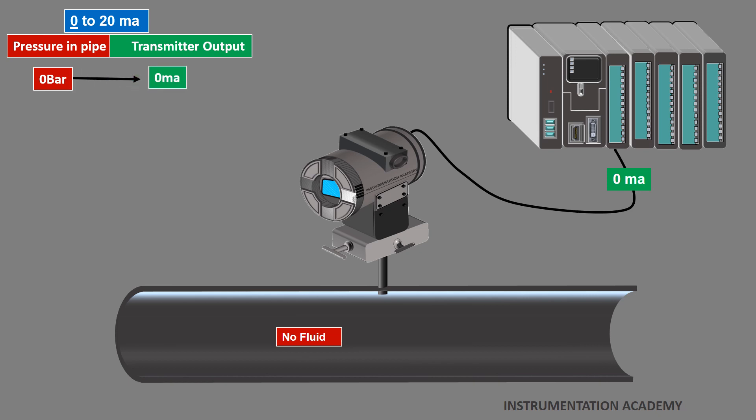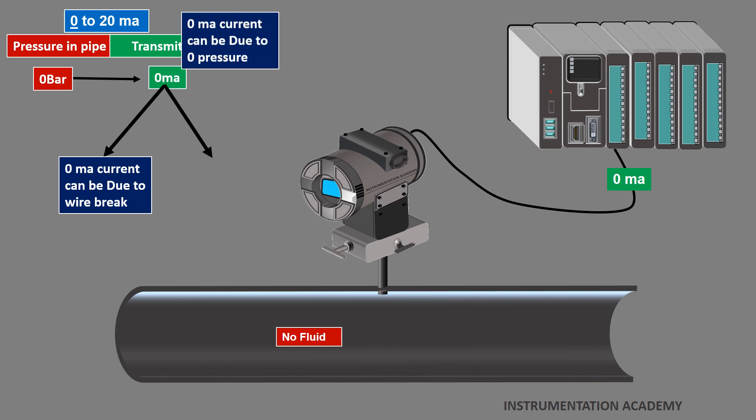In this case, it would be extremely difficult to identify that either 0 mA current is due to the wire break of the transmitter or it is due to no pressure of the fluid.